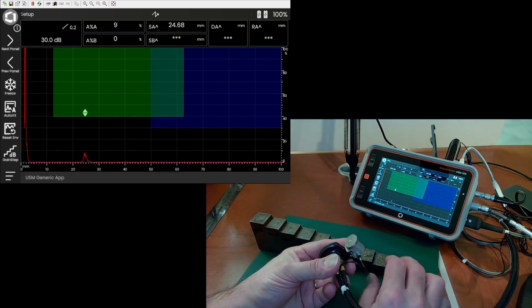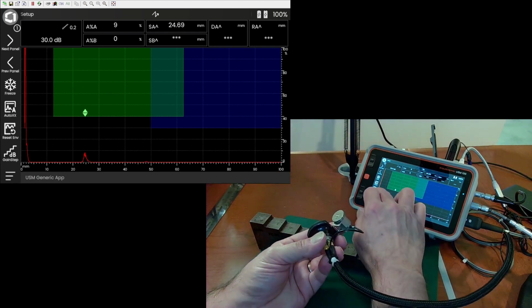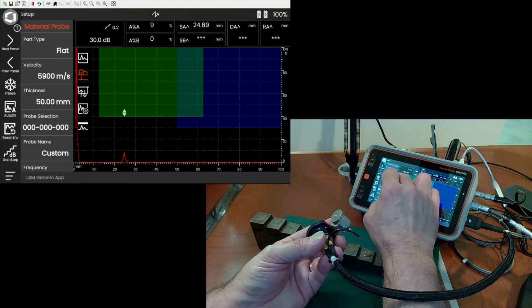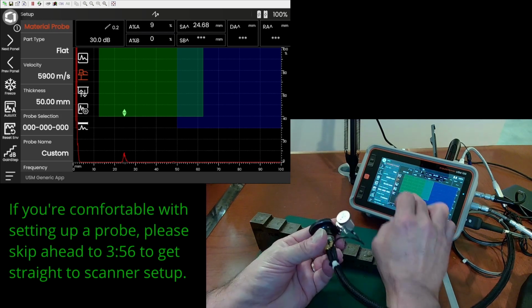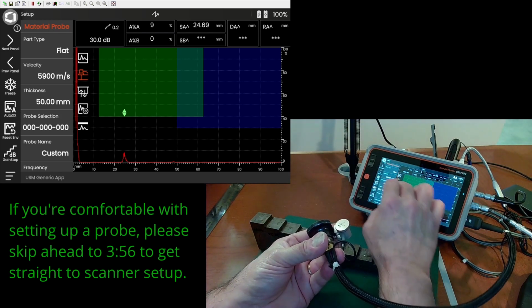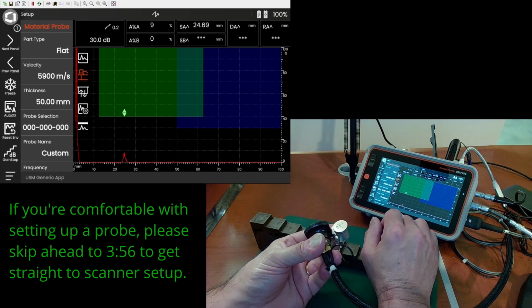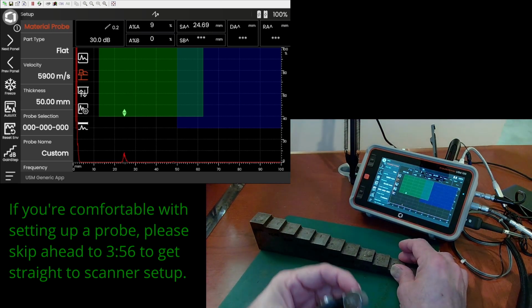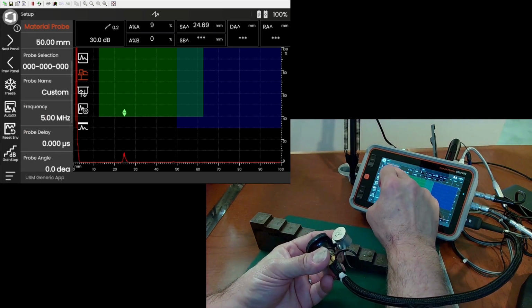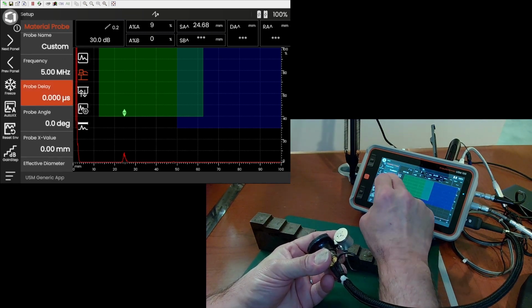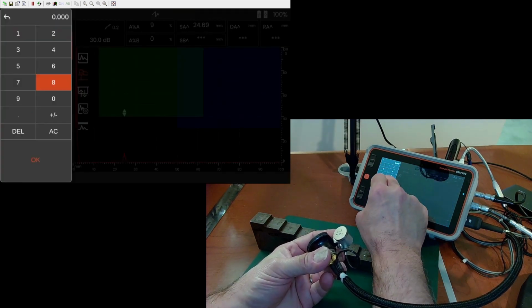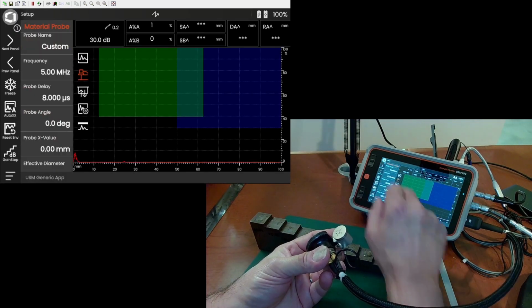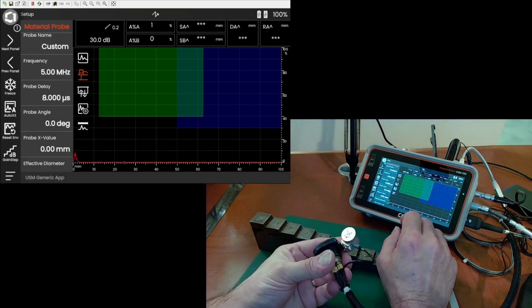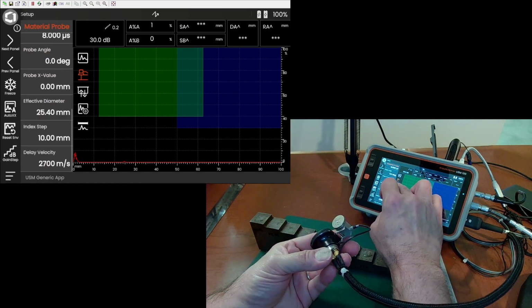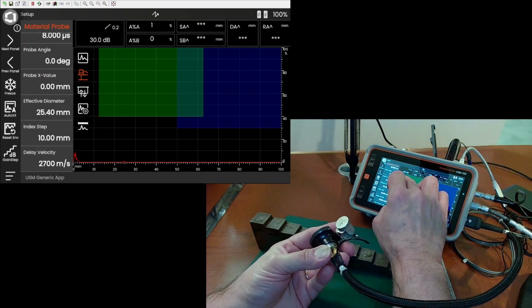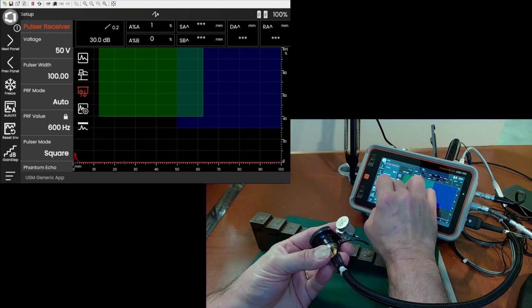So there I launched the app. We're going to start from scratch. First thing we're going to do is set up our probe. We are dealing with a straight beam probe, so 5,900 meters per second is good for velocity. We're going to be working with a carbon steel step block. My probe is 5 meg. I'm going to put an initial probe delay of about 8 microseconds in. That's going to be in the ballpark for this KBA 560. And we will not worry about anything else on that panel just yet.